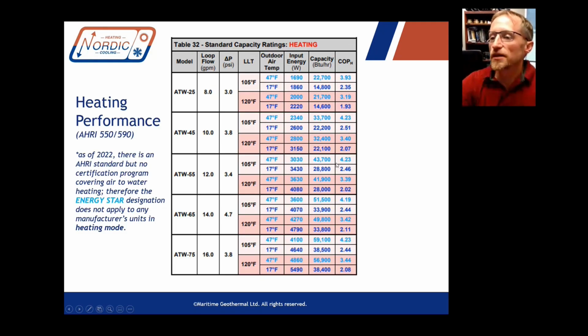For performance, there's a manual on the website that includes specifications. That's the best place to look for the performance of all the different models. The simplest performance chart to look at is the standard capacity ratings, and there's actually no AHRI standard for air-to-water heat pumps in heating mode yet. But when they update their standards, it's very likely that these temperatures will be used as the standard temperatures, because they're from other standards like water-to-water heat pumps or air-to-air heat pumps.